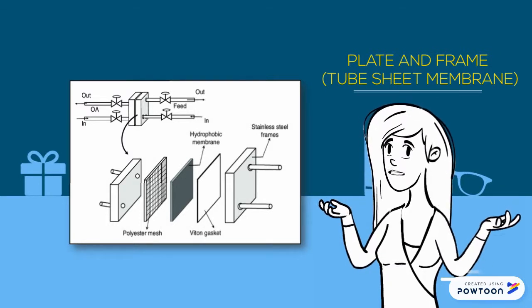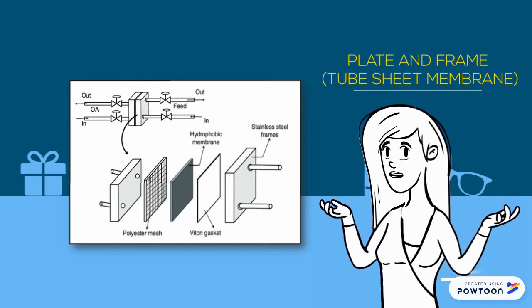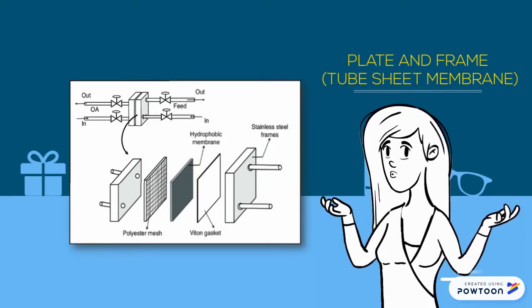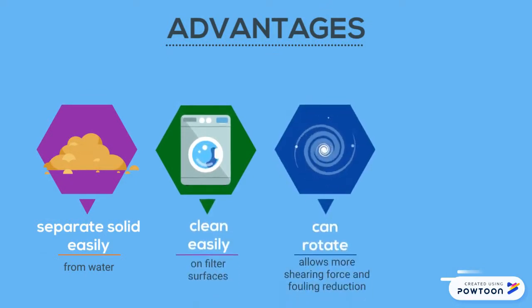Plate and frame membranes, also known as flat sheet membranes, utilize membranes laid on top of a plate-like structure held together by a frame-like support. Flat sheet membranes are bolted together with a frame around the perimeter. They work on the basic principles of cross-flow: feed enters on one side of the plated membrane, concentrate collects on the other end, and permeate travels through the membrane and collects on the inside of the supporting plate. Advantages include easy separation of solids from water, easy cleaning of filter surfaces, and certain configurations allow the plate and frame to be rotated for more shearing forces and fouling reduction.